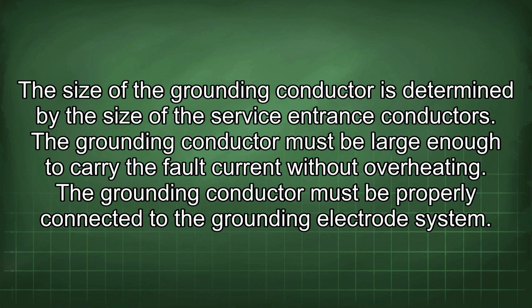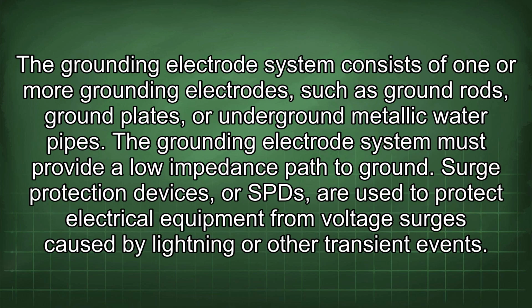The size of the grounding conductor is determined by the size of the service entrance conductors. The grounding conductor must be large enough to carry the fault current without overheating. The grounding conductor must be properly connected to the grounding electrode system. The grounding electrode system consists of one or more grounding electrodes, such as ground rods, ground plates, or underground metallic water pipes. The grounding electrode system must provide a low impedance path to ground.